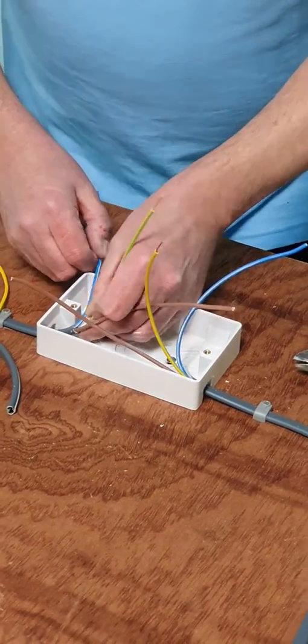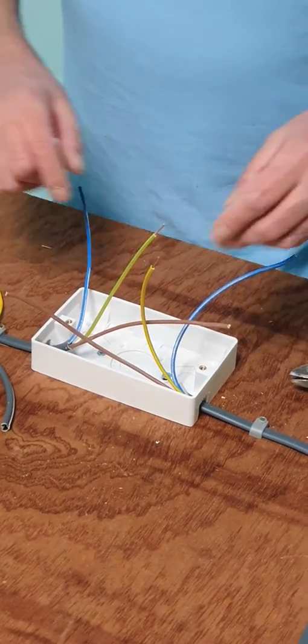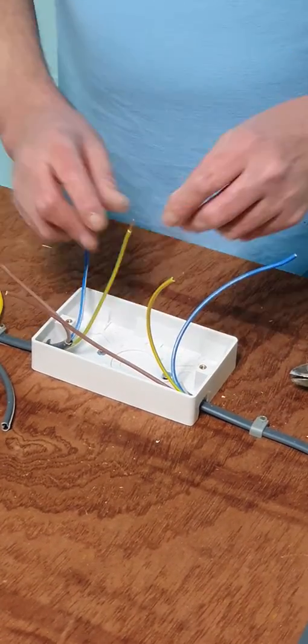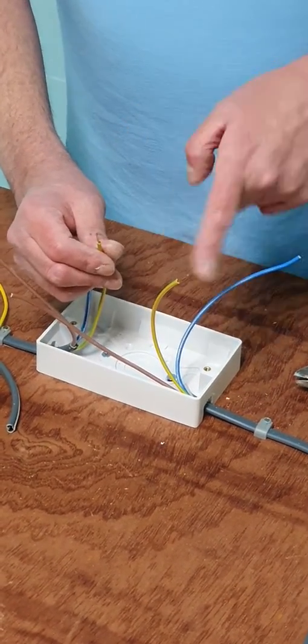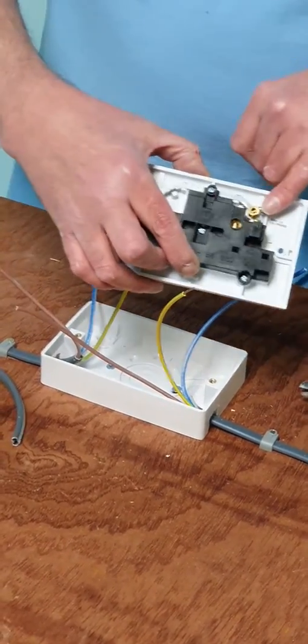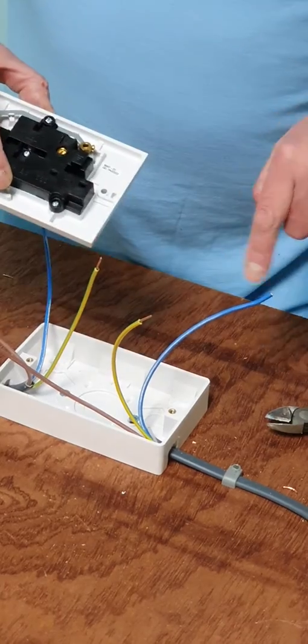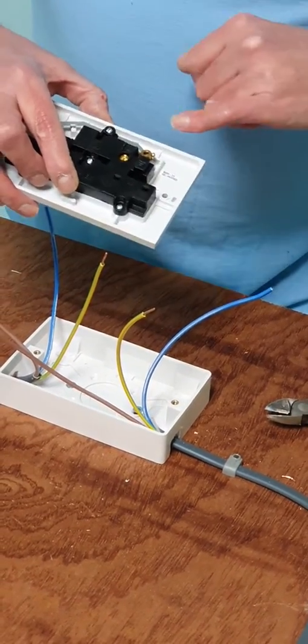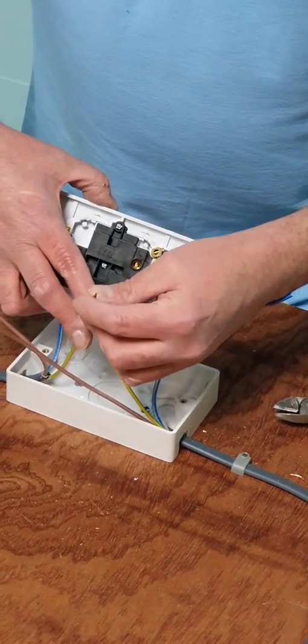Now as we're putting two conductors into one terminal. I know some people have a method of doubling this over and doubling this over. As you can see on certain types of sockets we're going to be quite tight to put two doubled up terminals in there. So two together going in the terminal is fine.